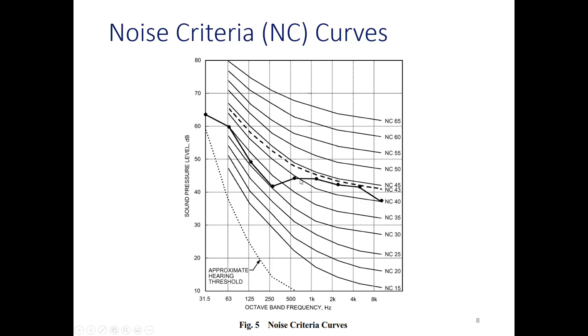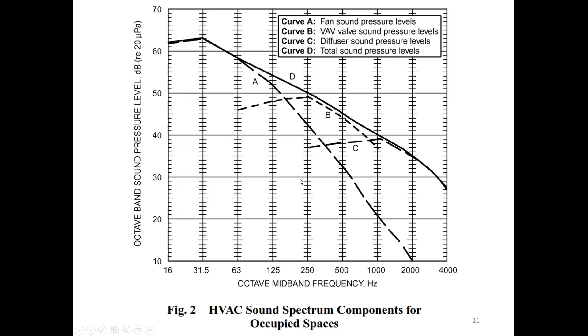So they don't necessarily track. What's shown here is just a middle of the road relation between these. I would say that your dBA could be as low as your NC, and it could be as much as 10 decibels higher. It's usually between those ranges. And remember, dBC just accounts a lot more for the lower frequency. It gives more weight to the lower frequency sound, so that's why higher values are possible over here.